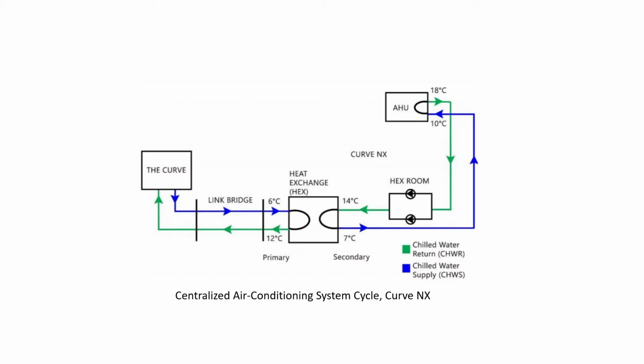So this is a diagram of the centralized air conditioning system cycle at Curve NX. At the Curve, the link bridge inlet is 6 degrees Celsius, and then it goes back at 12 degrees Celsius primary to the Curve, and heat exchange here, HEX. We have the HEX room at 14 degrees Celsius, then it goes up 7 degrees Celsius to the AHU room at 10 degrees Celsius, and then 18 degrees Celsius and to the heat exchange room. The green arrow shows the chilled water return, CHWR, and chilled water supply. It will supply, then it will return back to the system. It is like a closed loop system.